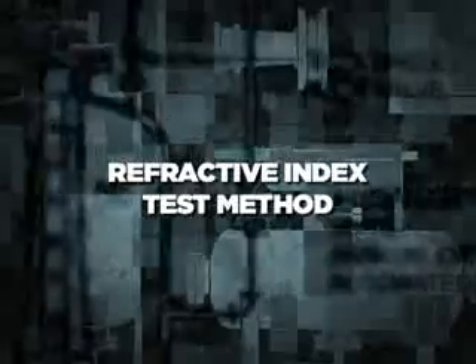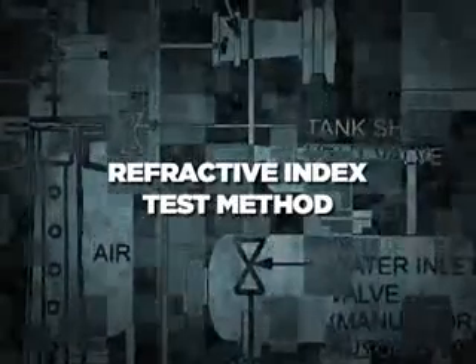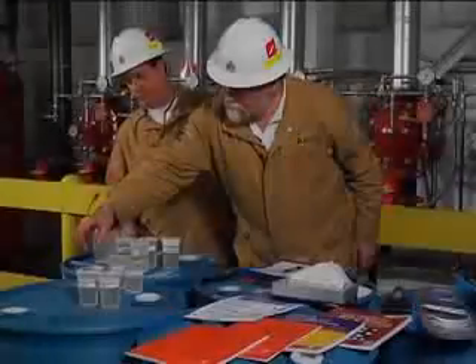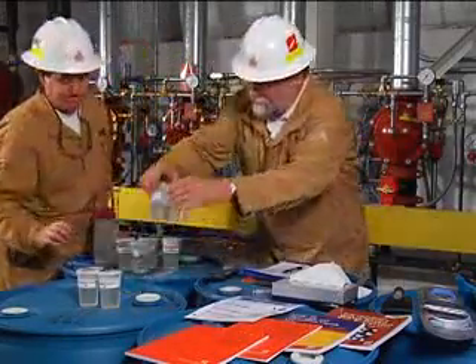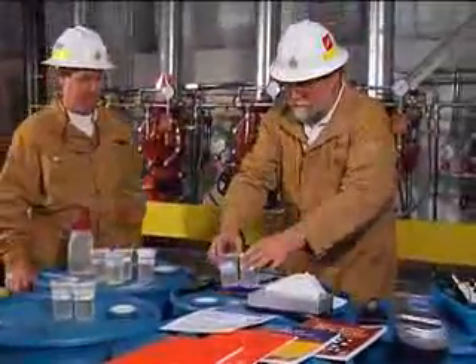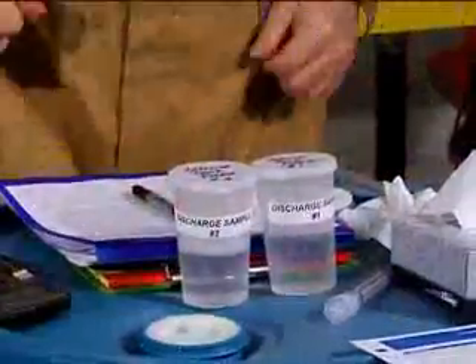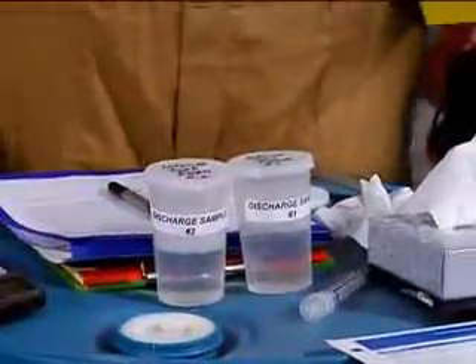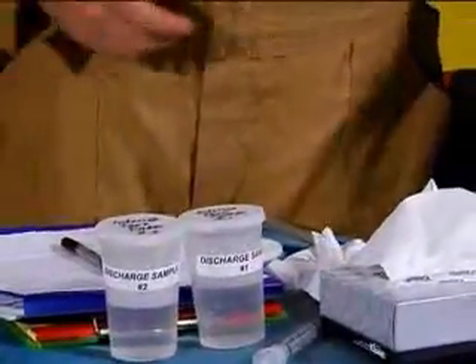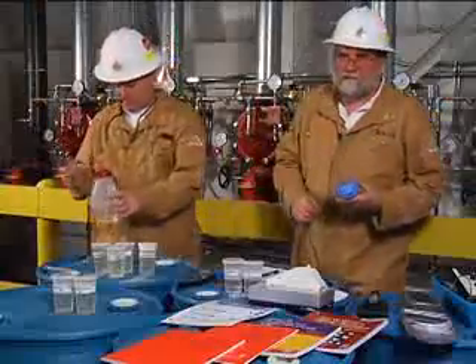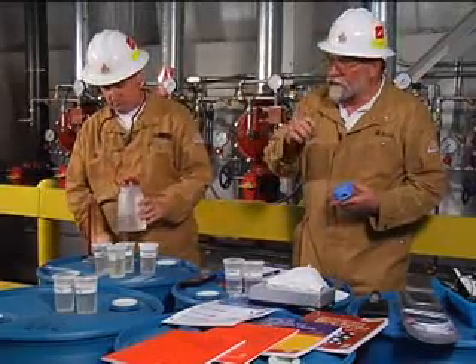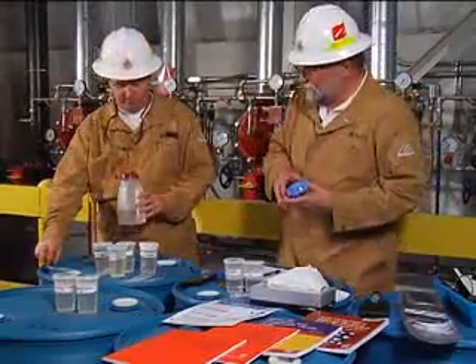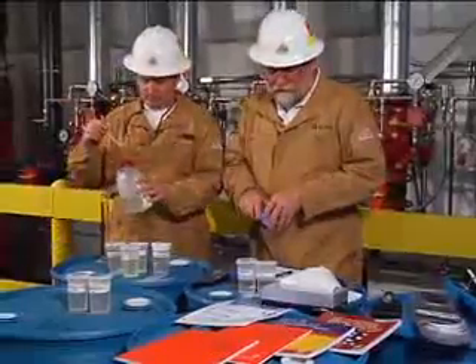Commission testing the Ansul bladder tank. Foam system testing, refractive index test method. We have the discharge samples that we collected when we did our test yesterday. And we're going to use a refractometer in this case to determine if our samples test out within the required 3 to 3.9% range as required by UL.